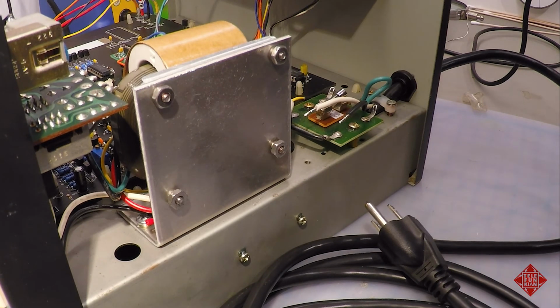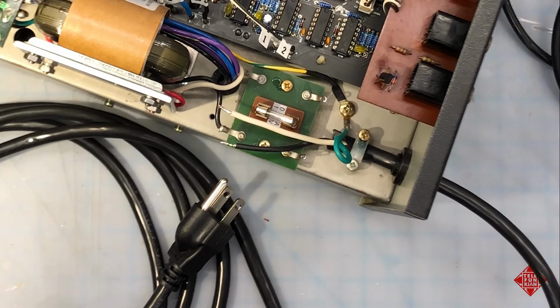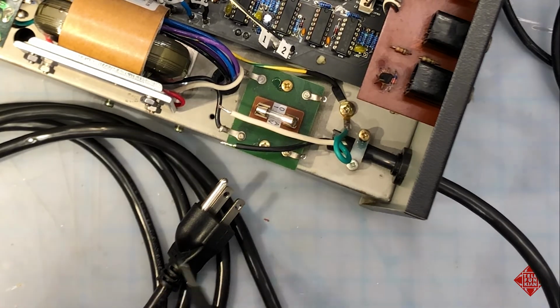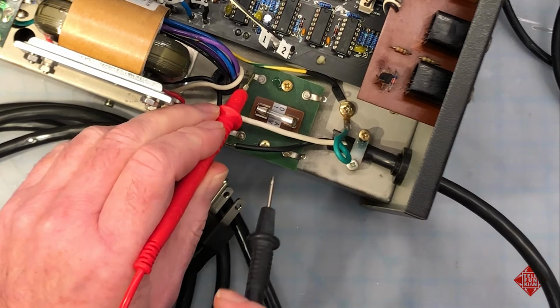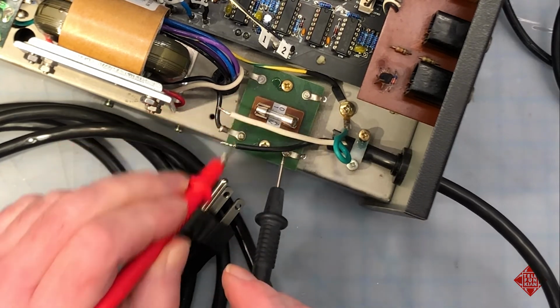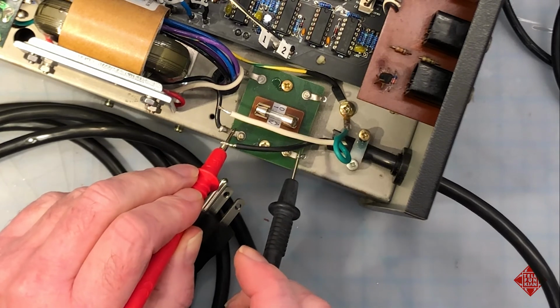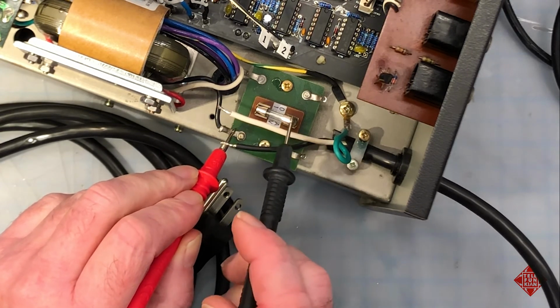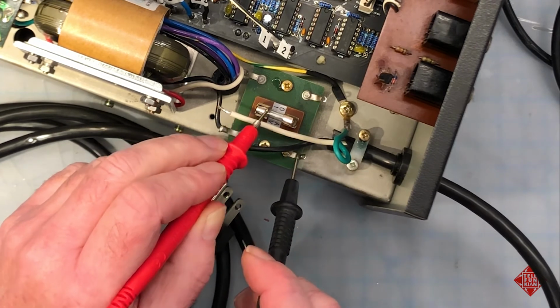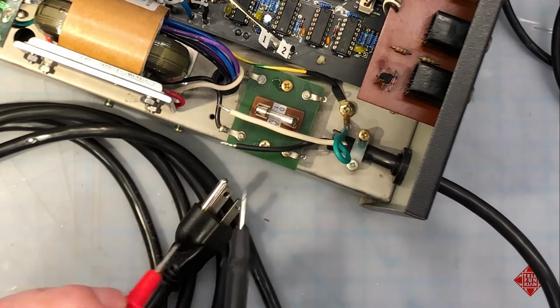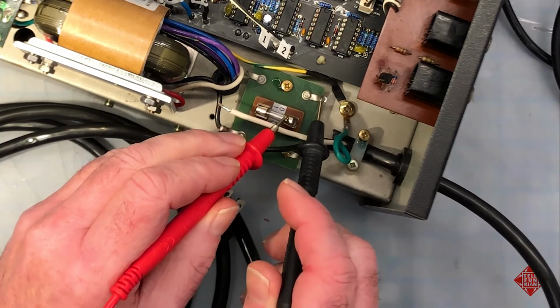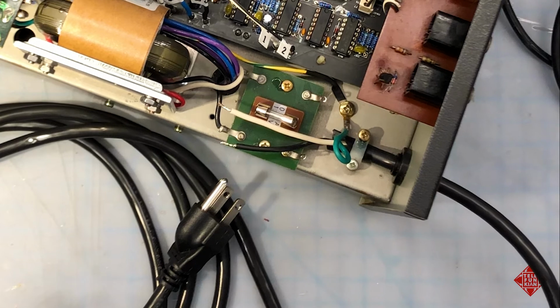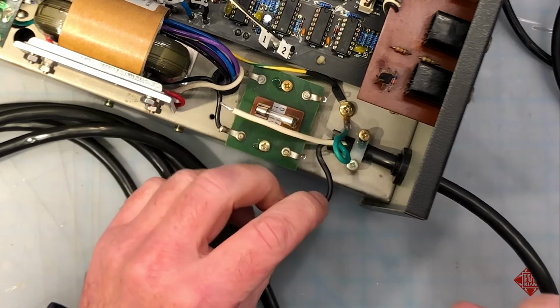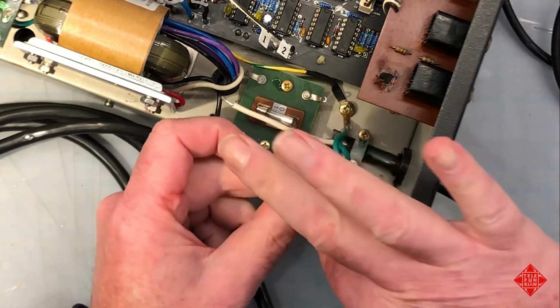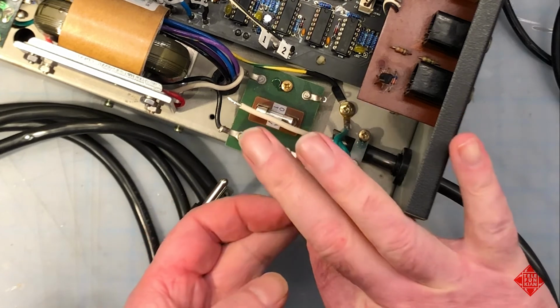And as a last check, we want to ensure that the fuse is actually on the hot line. And we see that it is. So the fuse is connected to the hot line and not to the neutral. And that's the way we want this wired. We want the fuse to be the first thing that the power is coming into contact with, the first thing that the power is going to see as it enters the instrument.